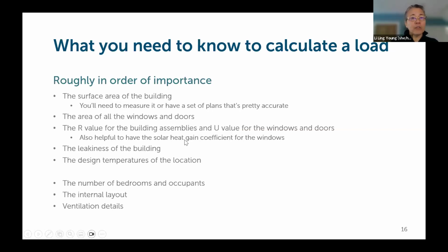You need to know the R values, which is the insulation in the walls and ceiling, but you also need to know the U values. The U value is the performance value for the windows and doors. There's also the leakiness of the building. You have to have some way of approximating the leakiness of the building, or if you've had a blower door test done, then the leakiness has actually been measured, and you can put that into the heat load calculation, along with the design temperature of the location where you are.